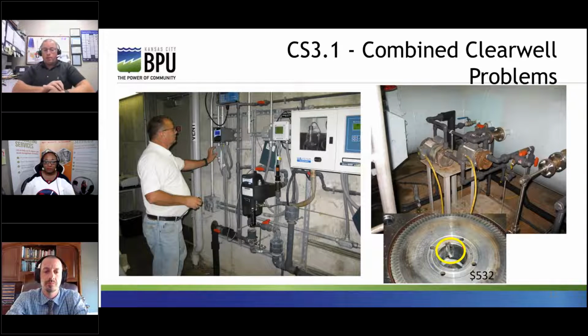Aeration of sample water to online turbidity analyzers. Sample point was too high on a pipe, but we didn't need to move it. And the turbine regenerative pump was serious overkill for the application. It was capable of pumping around 300 feet of head at 4 gallons per minute. So 2 solutions were employed to correct these defects.